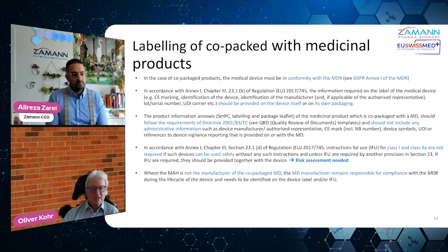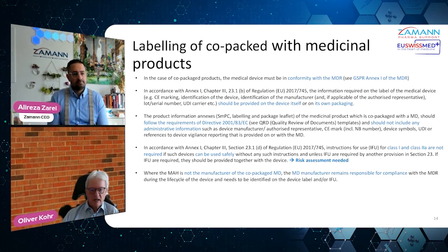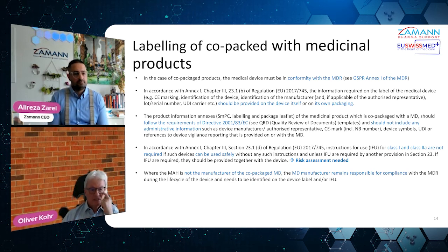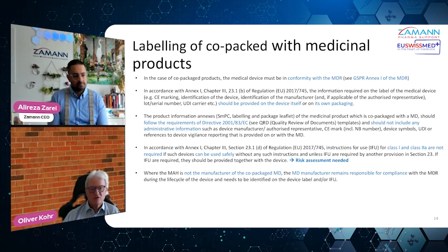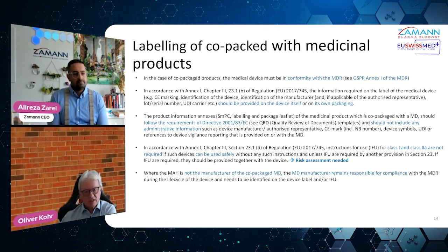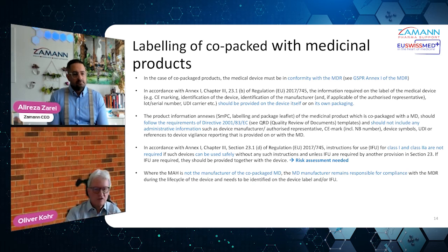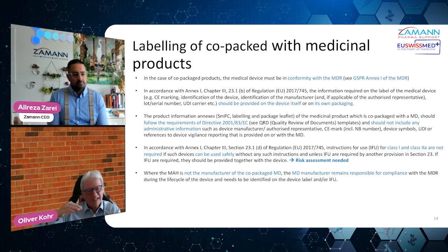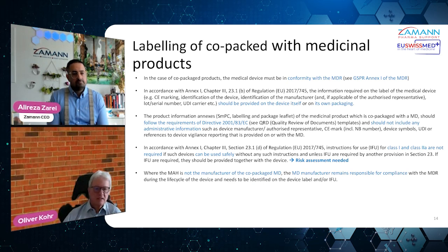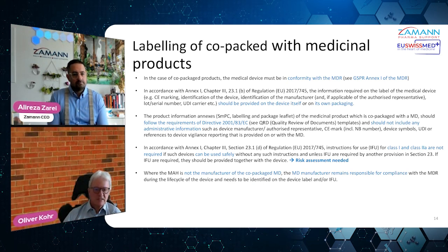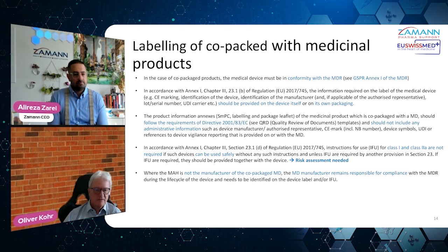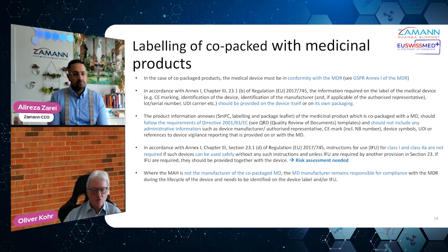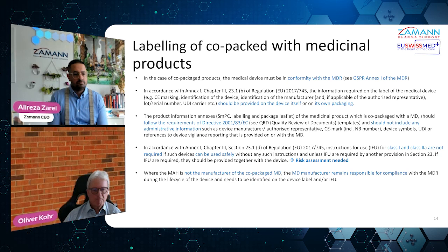These are some aspects of the labeling. In the labeling, I will not go through everything. You can read it. What's important is that you are aware of whether it is a medicinal product, and whether it is not integral. Then you know what the labeling aspects will be in the back. And there you have to consider Directive 2001/83, as well as the MDR, 2017/745. All right.